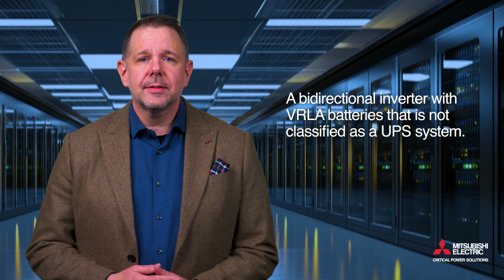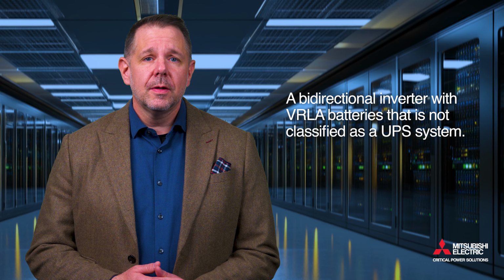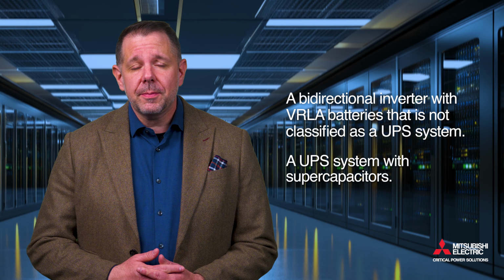Many different types of energy storage systems are required to meet UL 9540 standards to be NFPA 855 compliant, and those requirements vary depending on what kind of system it is. A UL compliant system could be a bidirectional inverter with VRLA batteries that is not classified as a UPS system, or a UPS system with supercapacitors. VRLA and lead acid batteries are included under certain stipulations in UL 9540. They are typically still exempt from having to meet the stringent fire safety standards requirements that other DC technologies do.